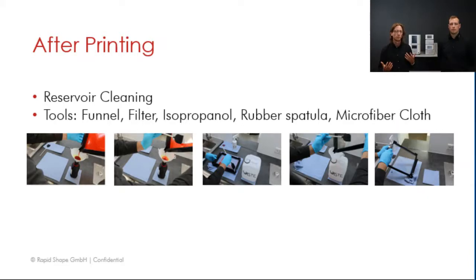So how to perform the reservoir cleaning? I just want to quickly walk through all these steps. You will also find the videos and the explanation online in our Knowledge Center, but just to get a brief overview about how to do that. As you can see, we need several tools. We need a funnel, we need a filter, we need lots of isopropanol, we need the rubber spatula and the microfiber cloth. So first step would be, we want to make sure that all the resin which is now trapped in the reservoir is filled back into the bottle. What we do here is we want to make sure that everything is getting filtered, because you could have some small cured elements or even some dirt or dust particles in the liquid, and we want to avoid having a contamination with the resin which is still in the bottle at the moment.